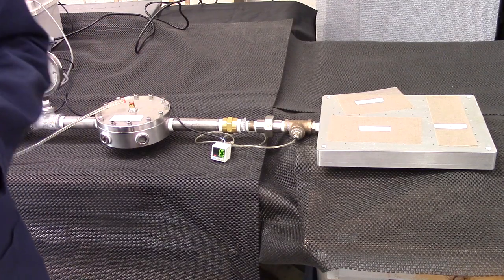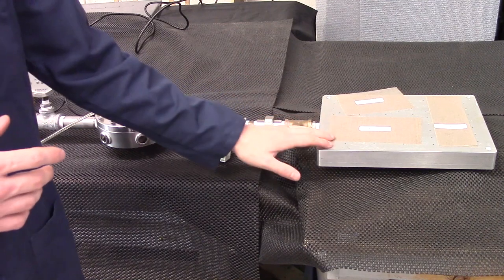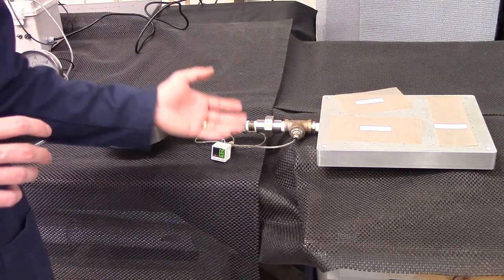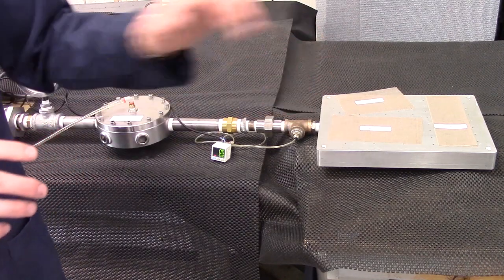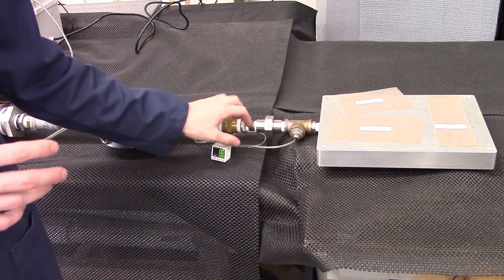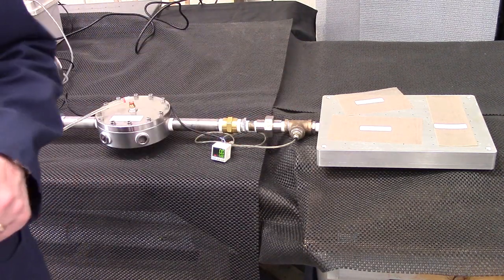Vacuum table and vacuum holding applications can be a challenge because the load changes quickly as products are placed on and off of a vacuum table. Consequently, the flow and pressure vary significantly with the number of open holes. Traditional systems using a percent open valve struggle to keep vacuum stable during these varying conditions, which can be detrimental to the product quality.